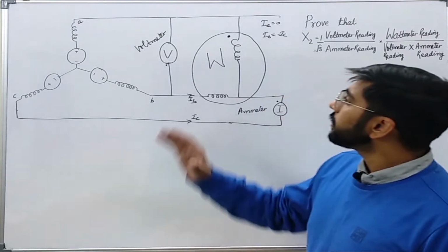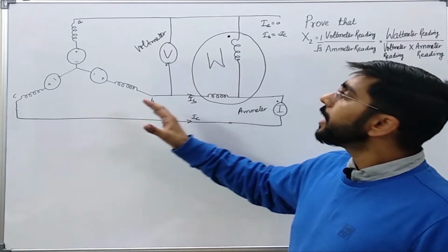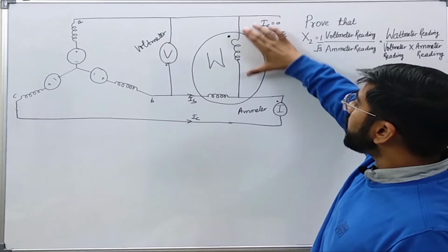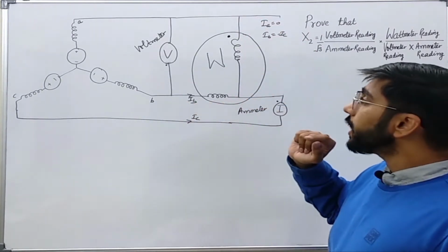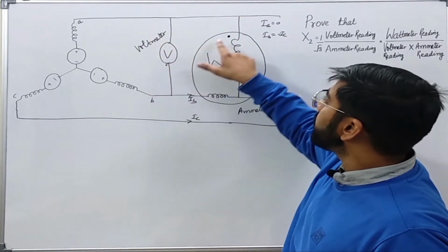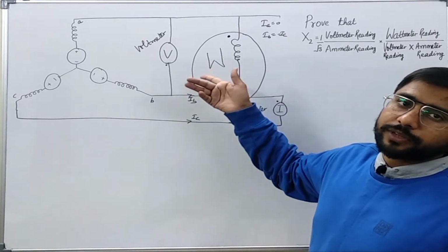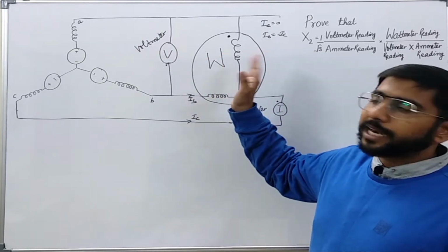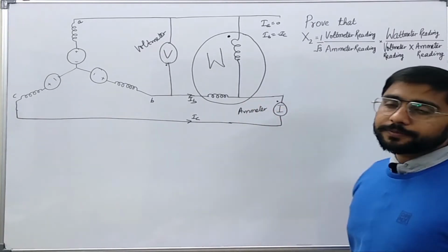using this experiment apparatus. In this, I have put a wattmeter with the potential coil between VA and VB and the current coil in the line IB. This voltmeter is measuring VBA. This dot signifies the polarity, although we can change the connections or terminals if any needle or meter is giving a negative reading. Similarly, this ammeter is reading IB.